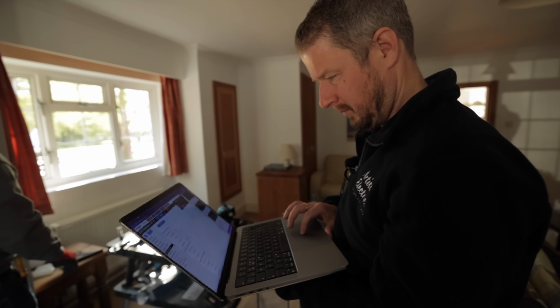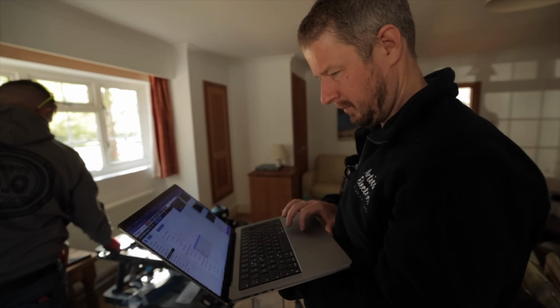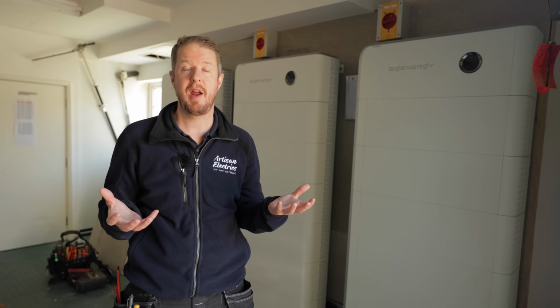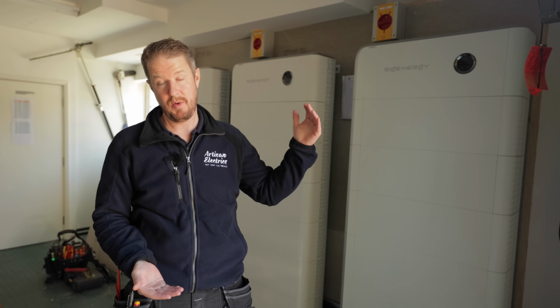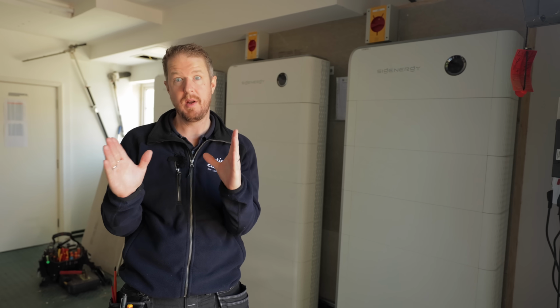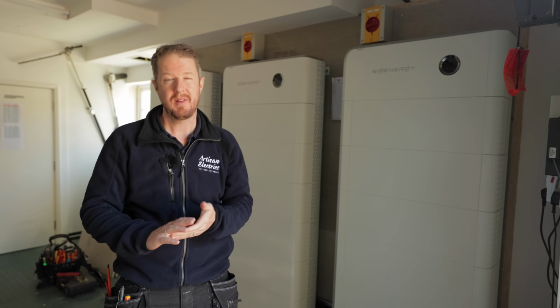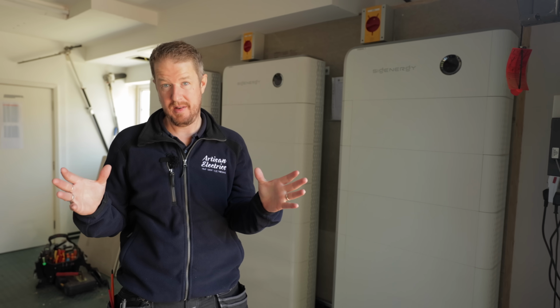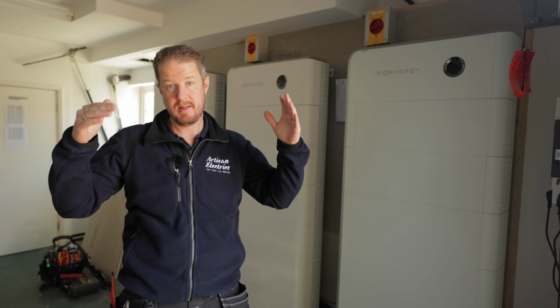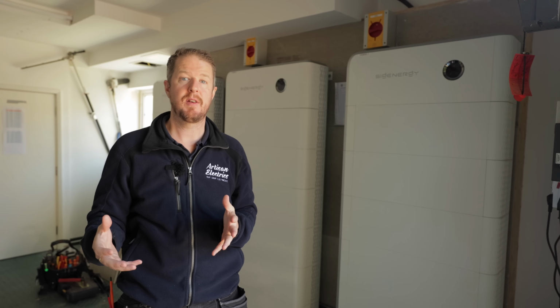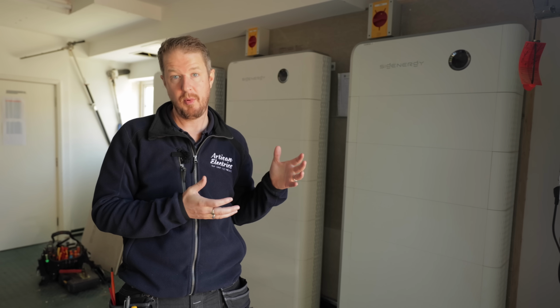Now, one of the most important things to factor in when designing a system like this is the charge time, because if you're planning the entire system around charging the batteries on the cheap rate overnight, you want to make sure that you can actually charge all of these batteries up within the window that you've got of cheap electricity. So for example, most people have a 5-hour window. So you can size the inverters and the batteries, taking into consideration the maximum charge rate of the batteries to be able to be filled up within that time.